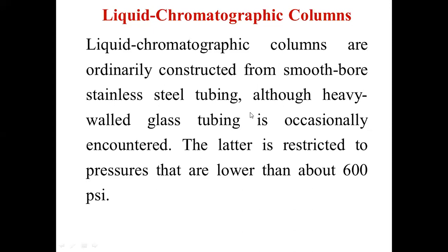So the liquid chromatography columns are normally constructed of stainless steel. They are also heavy walled glass tubes, and the glass tubes are restricted to pressures up to only 600 psi, because they are prone to break. Therefore, if we want to use the column at a pressure above 600 psi, pounds per square inch, we cannot use the glass columns, but we can use stainless steel columns when the pressure is going to be maintained beyond 600 psi.